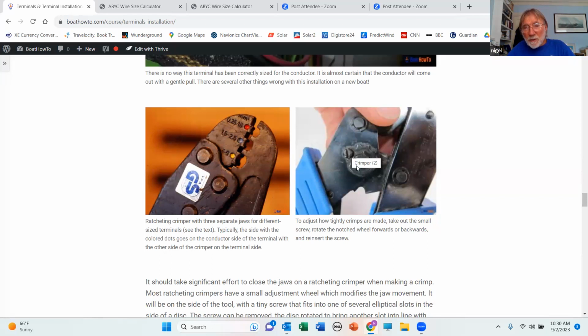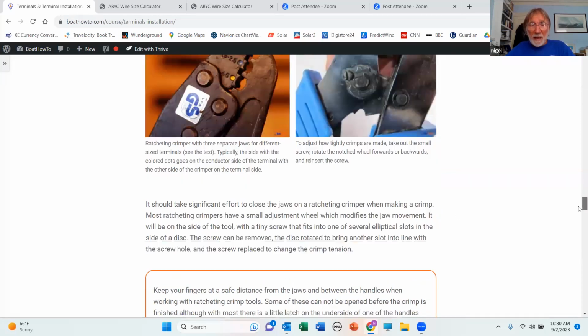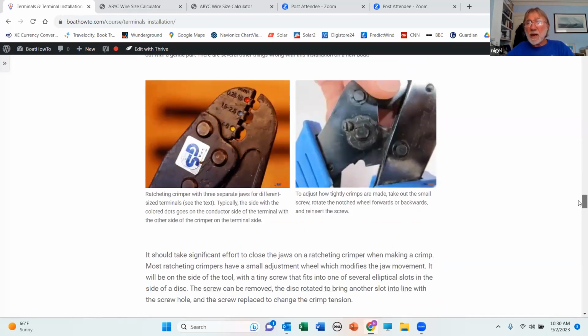And if you take this screw out and turn the wheel and put it back into another one of these slots, you can either tighten or loosen the crimping action of the crimper. I've discovered over the years that most people don't realize that's there. So go ahead, do some practice crimps, pull them apart, tighten up the crimper. The arrow will show you which way is tighter. It says positive there and negative. And then try again until you know you're doing basically bulletproof crimps. And pull on those things as hard as you can.